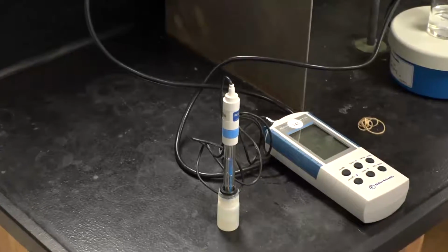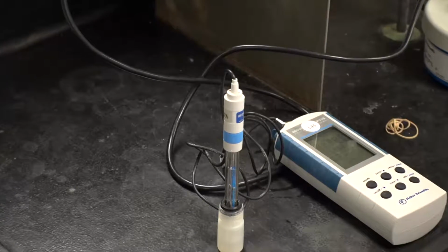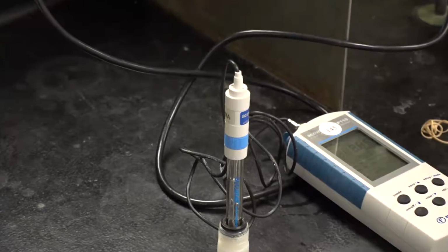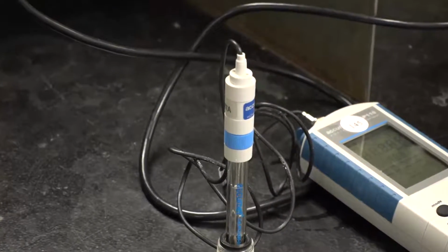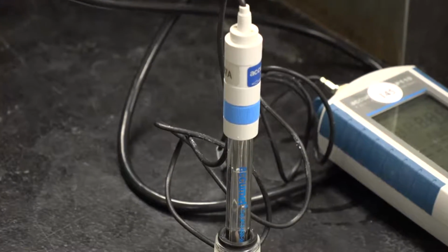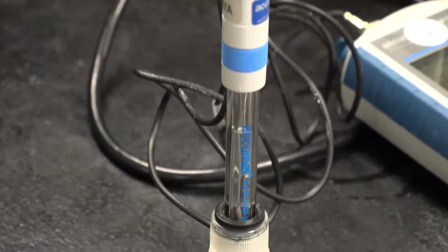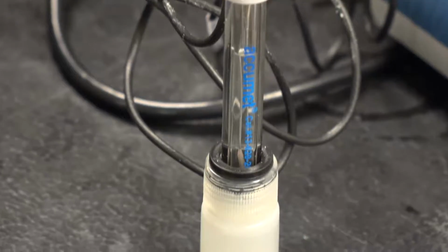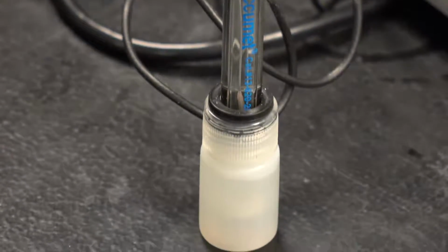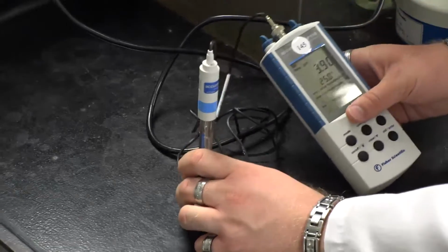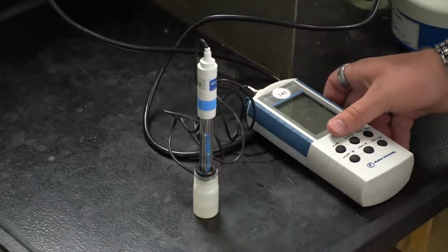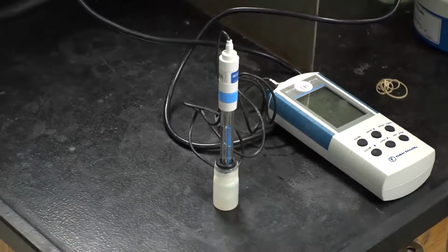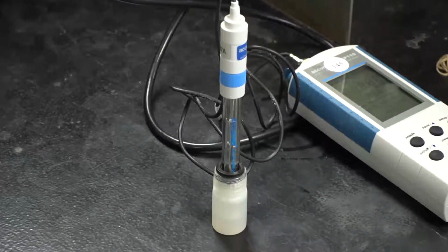The probe you will use is a silver chloride, potassium chloride electrode. The probe uses glass that allows hydrogen ions to permeate the membrane. We measure the potential difference in the solution outside the glass compared to the electrode solution inside the probe to measure the pH. The probes are fragile and each one can cost up to $300 to replace. We want to be sure to handle the probes and the meters with care.